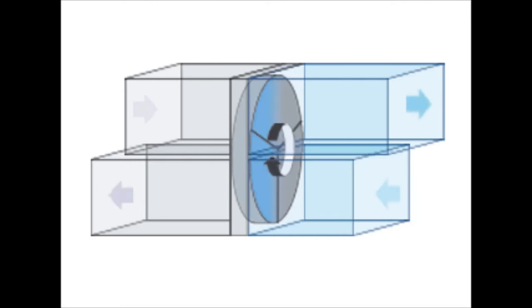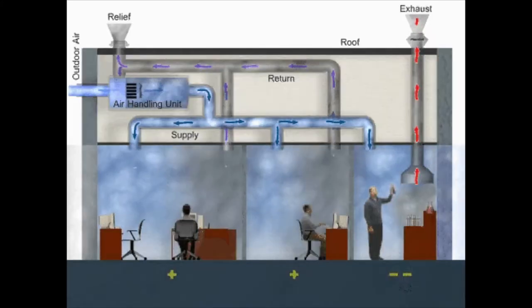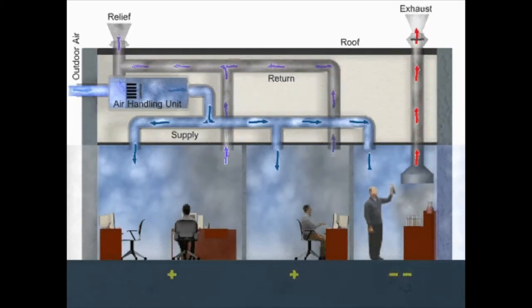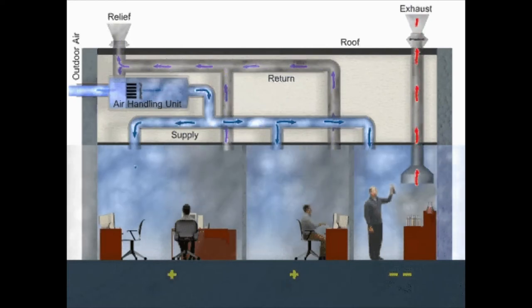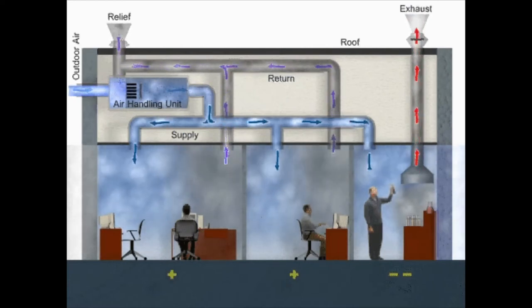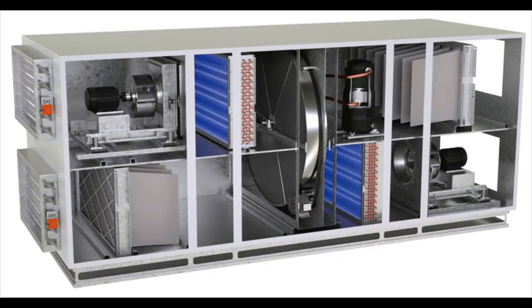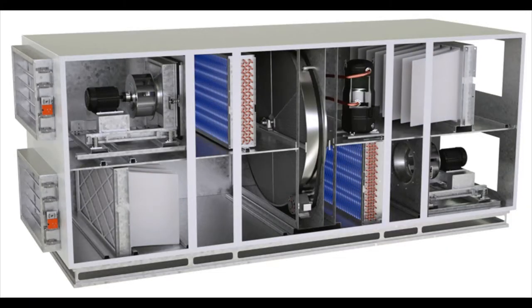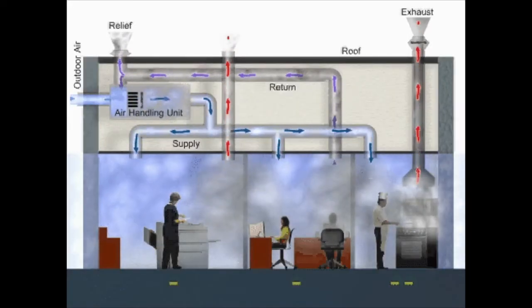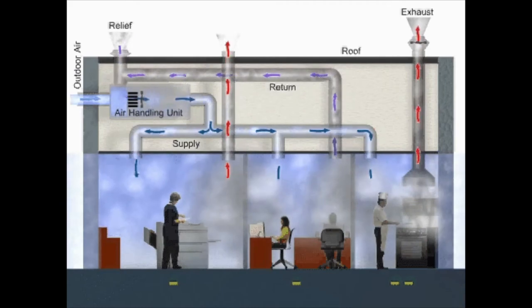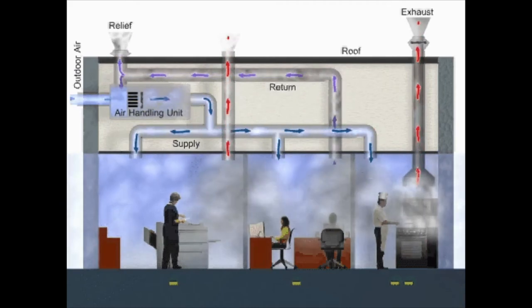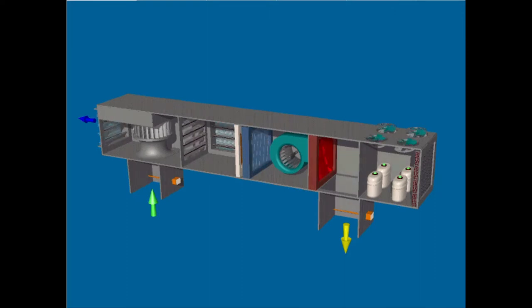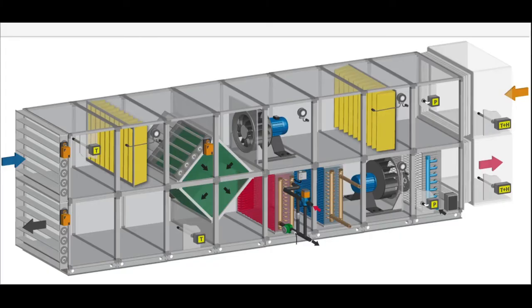But rooms are usually not that small. Say a room is 100 by 100 square feet by... what is it, Joe? If it's 100 by 100, that's 10,000, by 10... 100 feet is a lot, isn't it? Yeah, that's a pretty big space. So it's 100,000 cubic feet of volume in that space. But that doesn't necessarily mean that the CFM will be that much. CFM will be a lot less than that, somewhere between 2 air changes to 10 or something.